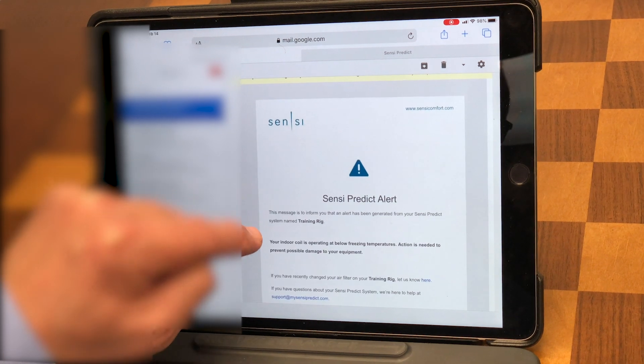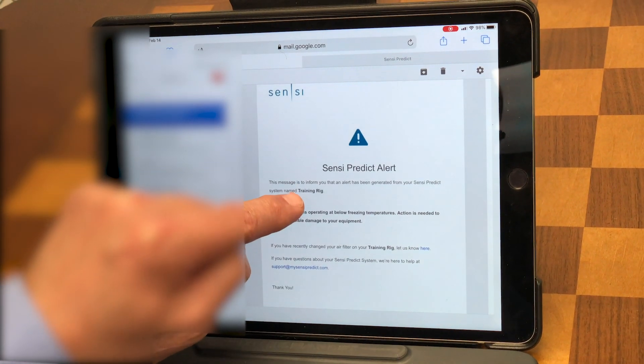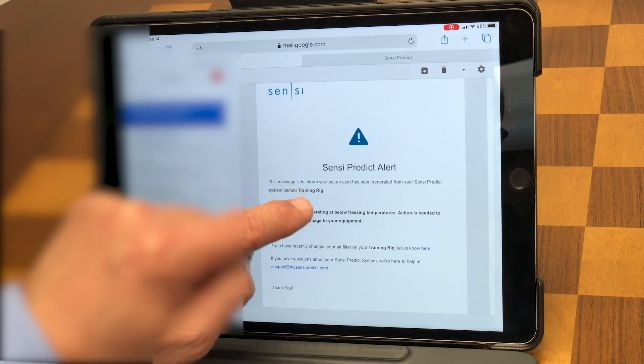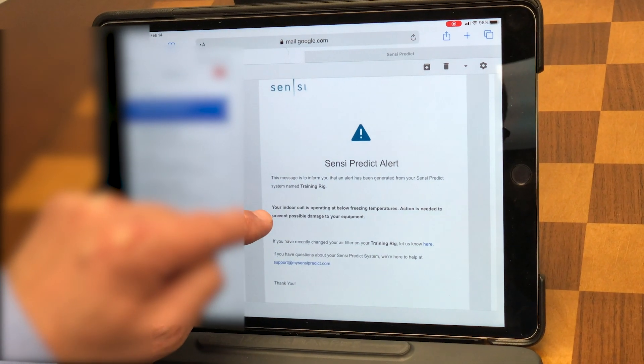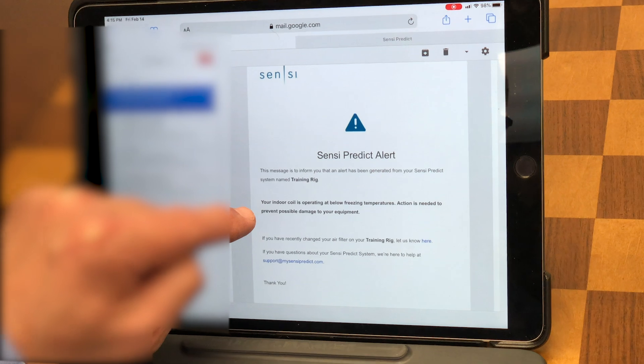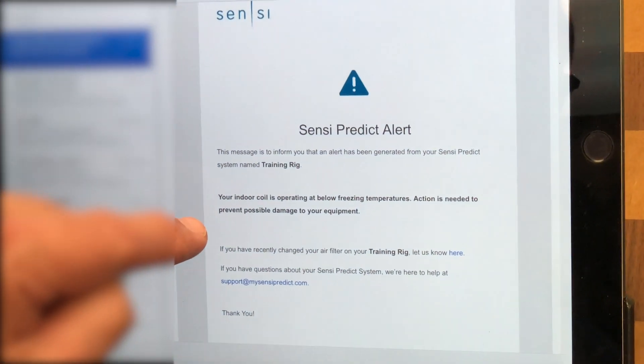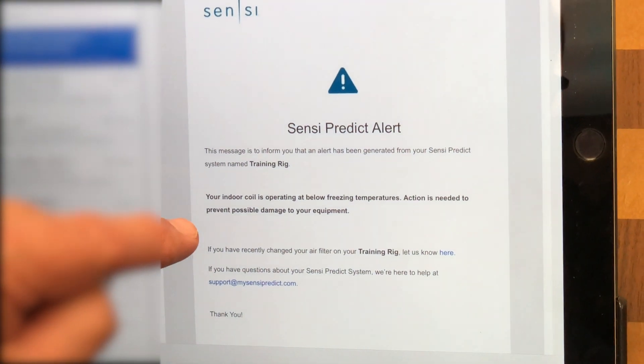It tells you the customer, and this one here is named Training Rig — it's going to be Bob Jones or whoever the customer is. Then it gives us what the alert is: the coil is operating below freezing temperatures, and action is required to prevent possible damage to the equipment.